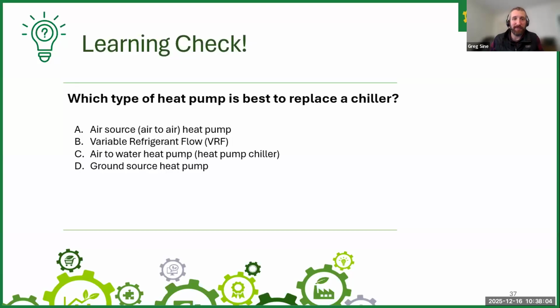So this one, in my mind, the best answer would be C, air to water heat pump or heat pump chiller. That could be considered a drop-in replacement and get some immediate decarbonization, even if it can't fully supply the heating load for the space. So, thinking about your buildings, a good early stage opportunity for decarbonization would be buildings that have aging chillers that may need to be replaced soon. We try to identify those as a high priority item, both in the PPP and CBA studies.